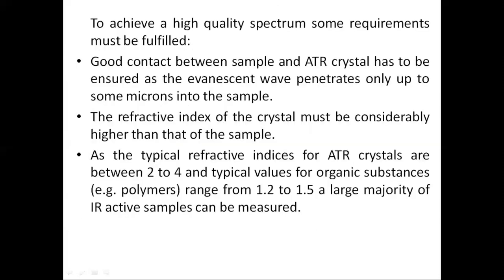To achieve a high quality spectrum, some requirements must be fulfilled. Good contact between sample and ATR crystal has to be ensured, as the evanescent wave penetrates only up to some microns into the sample. The refractive index of the crystal must be considerably higher than that of the sample, as the typical refractive indices for ATR crystals are between 2 and 4, and typical values for organic substances, for example polymers, range from 1.2 to 1.5. A large majority of IR active samples can be measured.